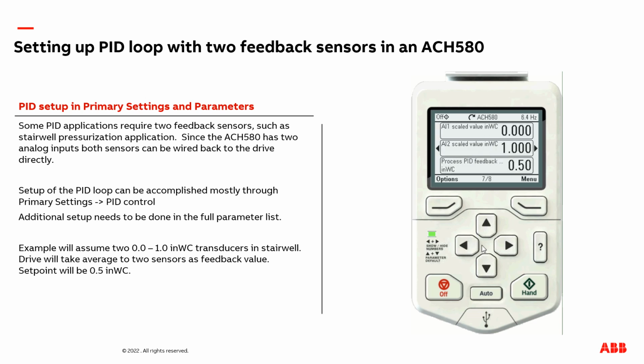I pre-set up initially here for this presentation another menu, and you can make these adjustments by clicking options and going to edit home view. As you can see here, I have AI1 scaled on top, and I also edited the text to add inches of water column, and I have AI2 scaled in inches of water column, and then I have the feedback. So the bottom value is the combination, the average, because that's why I selected the average of both AI1 and AI2. As you can see, I have 0 and 1 inch of water column. The average of that would be a 1/2 inch of water column.